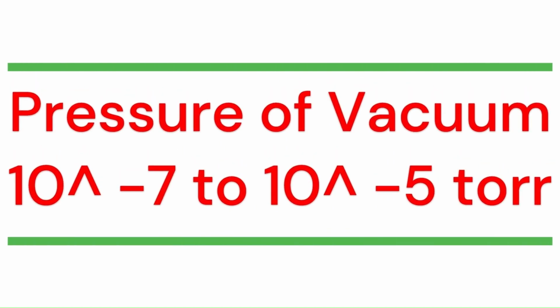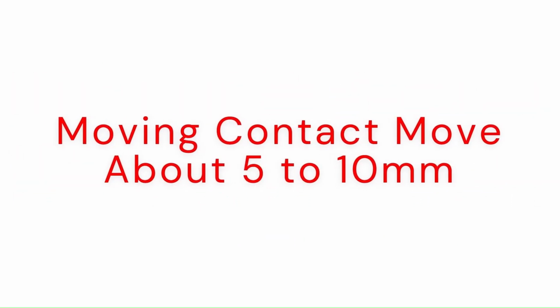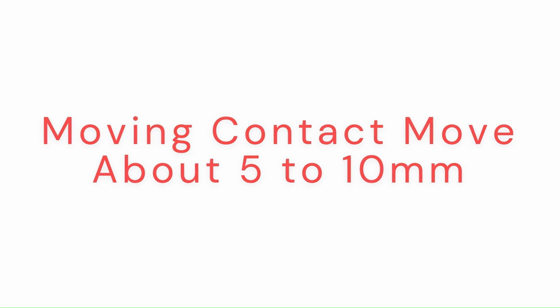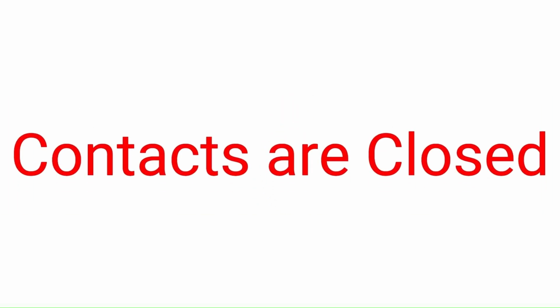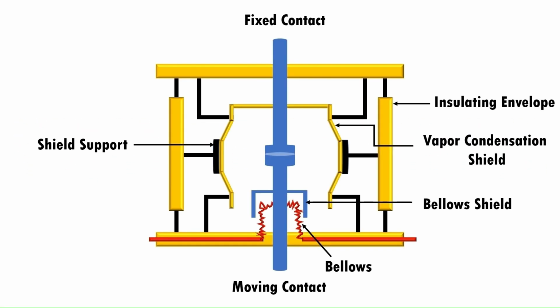The pressure in a vacuum interrupter at the time of sealing is kept about 10 raised to minus 7 to 10 raised to minus 5 torr. The moving contact of the circuit breaker moves through 5 to 10 mm depending upon the operating voltage. Now we will see working of vacuum circuit breaker. At the time of normal operating condition, fixed contact and moving contact are closed.